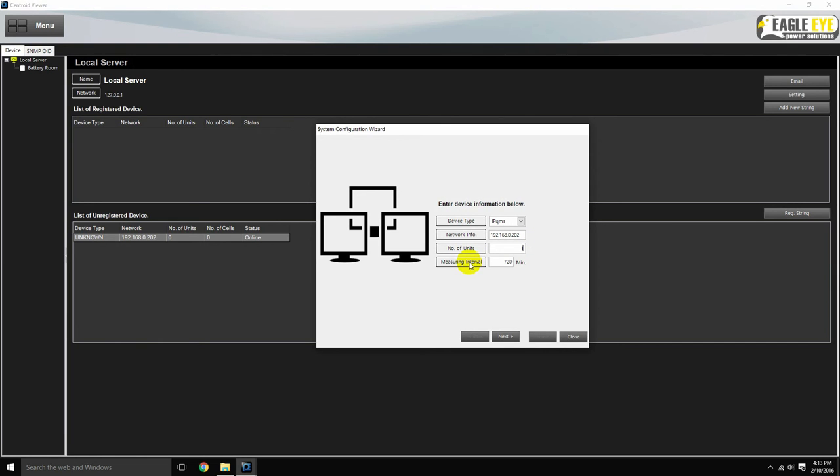The measuring interval refers to how often the resistance measurement is taken in minutes. We recommend 720 minutes, which is twice per day.